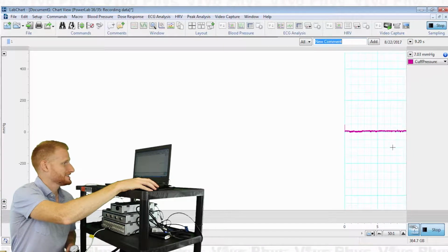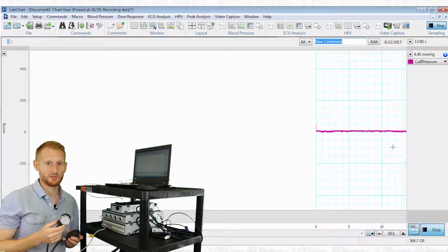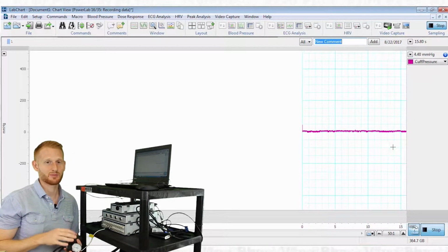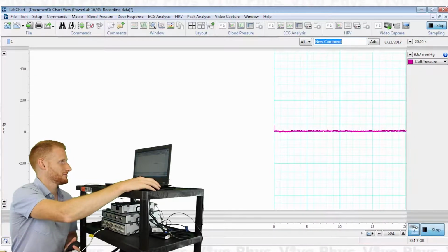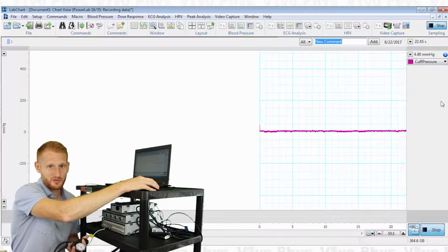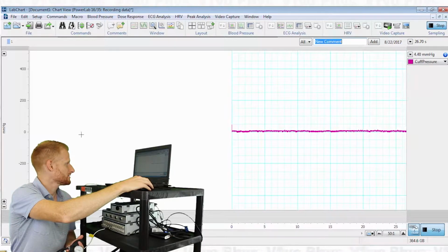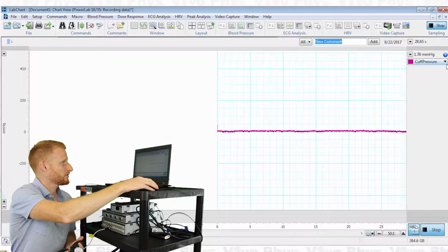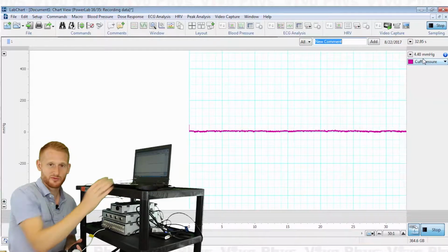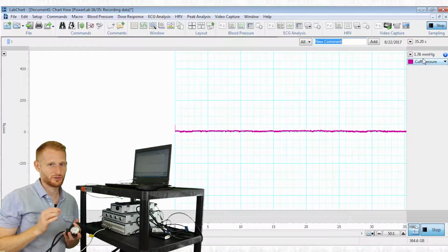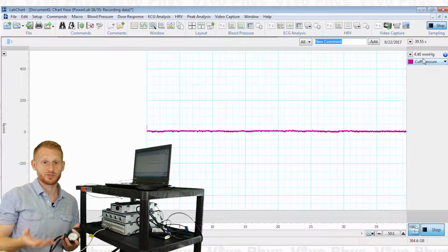It's somewhere near zero, so this is why I said this probably isn't the best for doing accurate blood pressures. This has been calibrated recently, but it's got a little bit of a drift. I guess it was calibrated maybe a month or so ago, so it's drifted a little bit in that time, but it's somewhere near the zero line there. But if we look up here, we're seeing some sevens, some nines, occasionally some fours or zeros in there, so it is a little bit off.